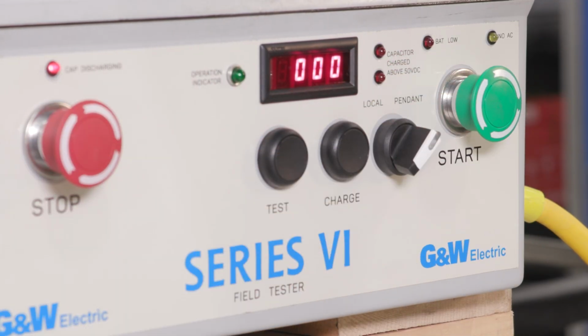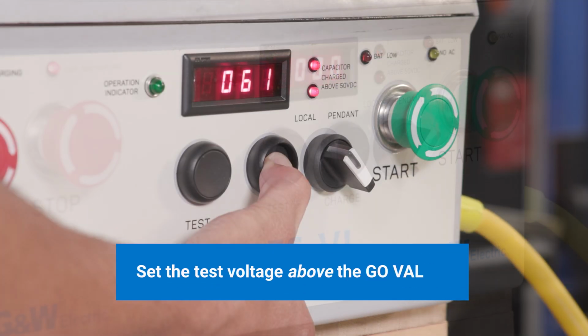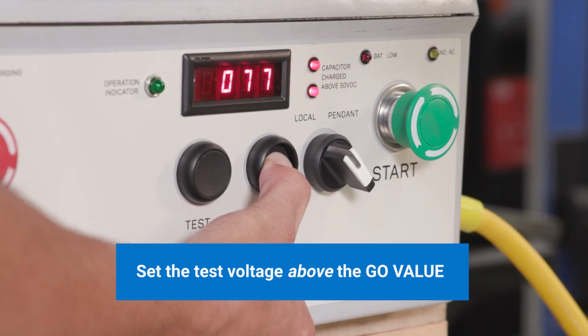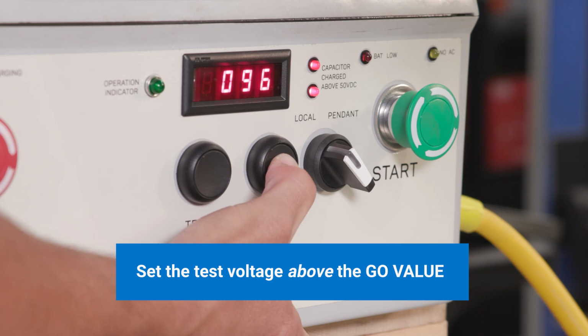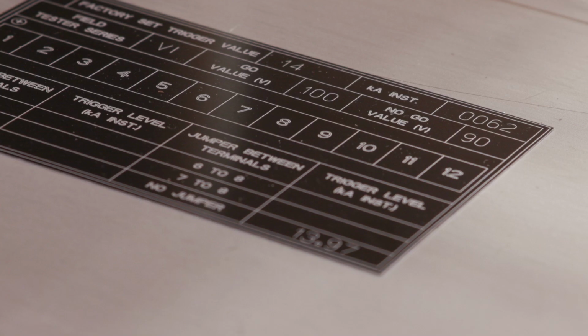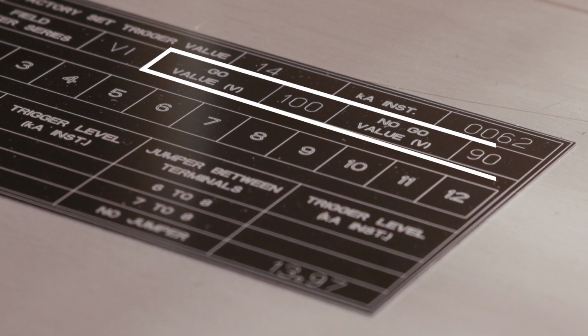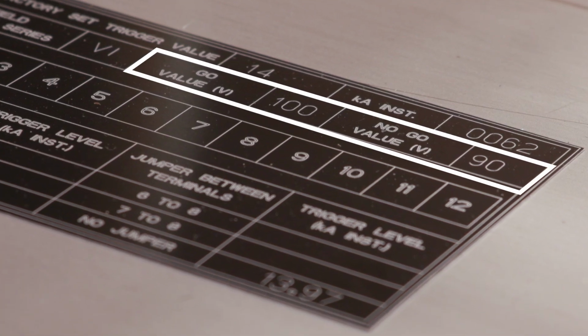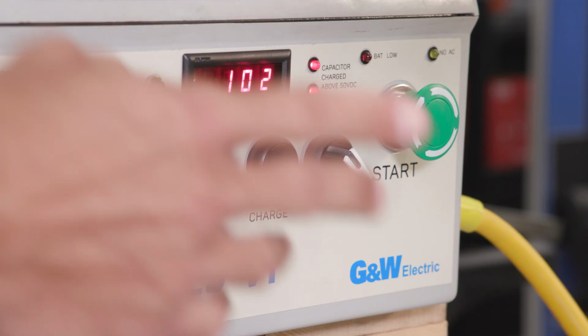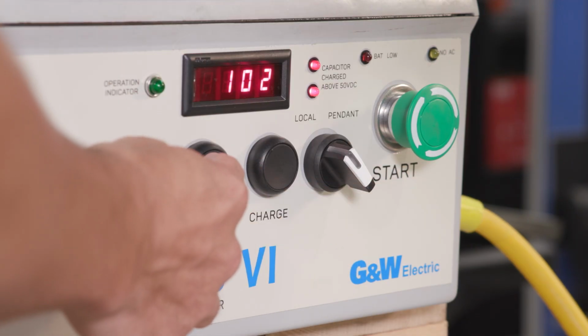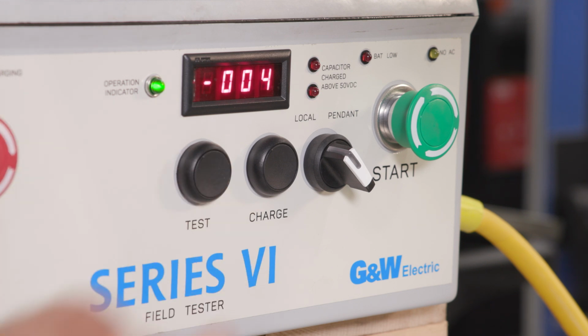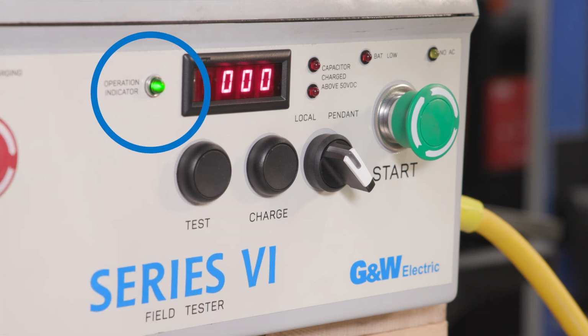Now set the test voltage above the go value by pressing the charge button and holding it down until the voltmeter indicates the proper voltage based on the trigger level of the CLiP current limiting protector. This voltage value is shown on the black nameplate on the base of the unit. Next, press the test button and verify that the SFL is fired. The field tester green LED will illuminate with a successful triggering event.